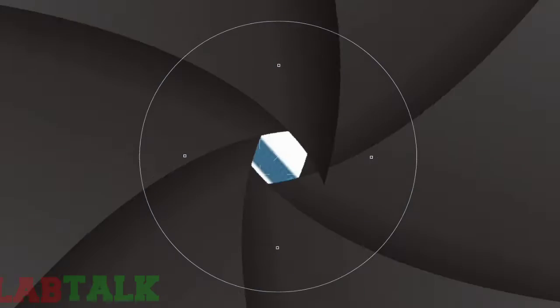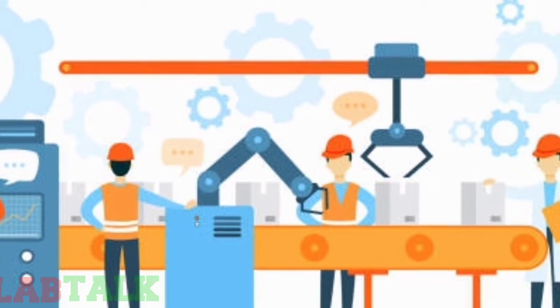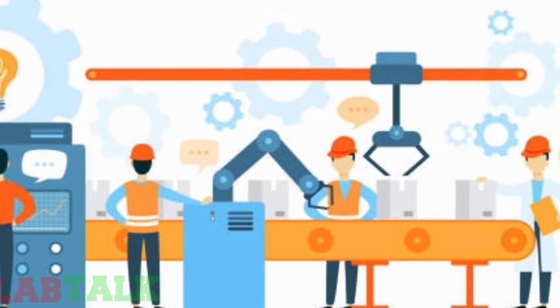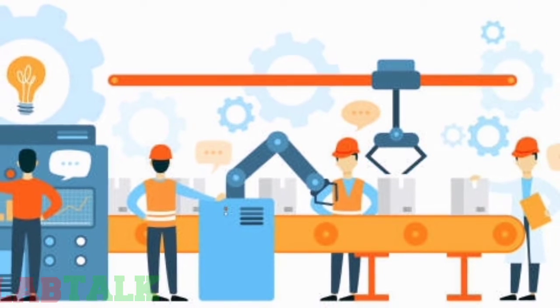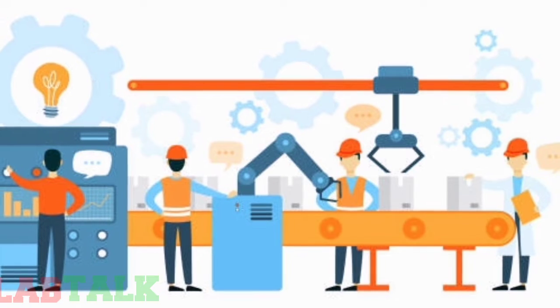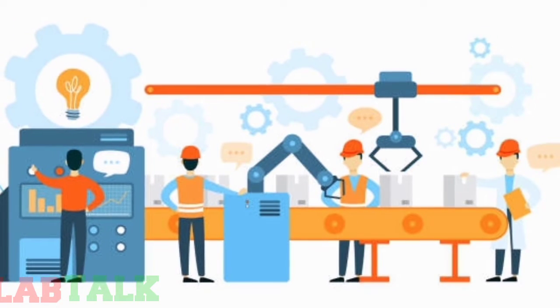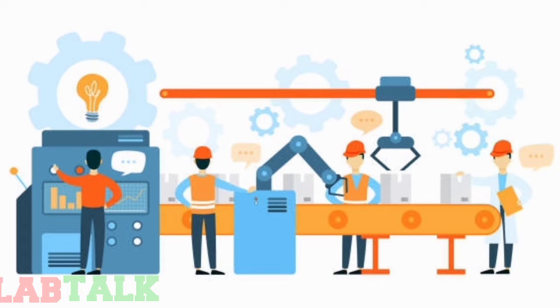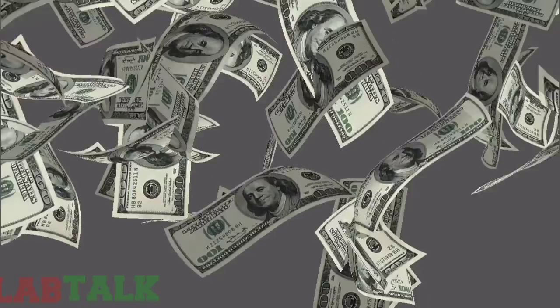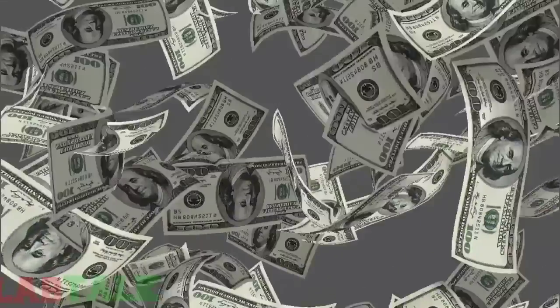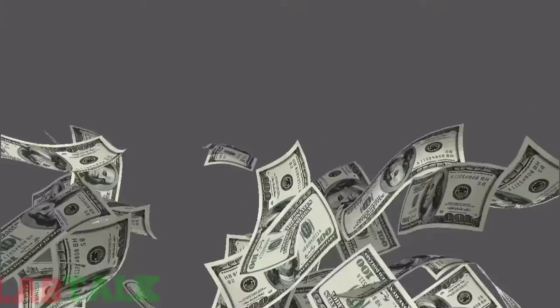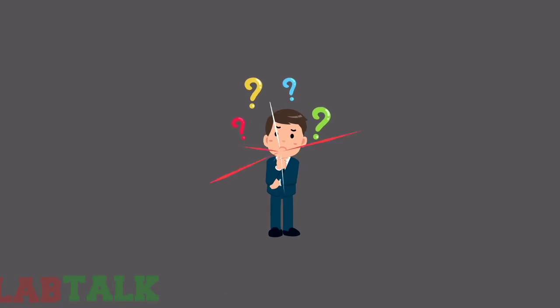In this series of videos, I will include the protocols for installation qualification, operational qualification, performance qualification, how to document it all, that is document qualification, and design qualification related to the equipment in the clinical laboratory. It is seen at many places that the vendors are just selling the equipment without doing the proper qualification of the equipment or without verifying the equipment qualification, and the lab is left on its own. So to verify the equipment performance, it is required to perform the proper qualification of the equipment.